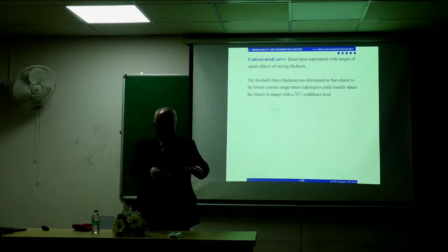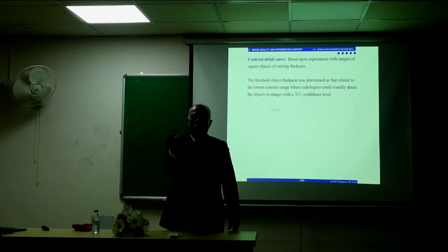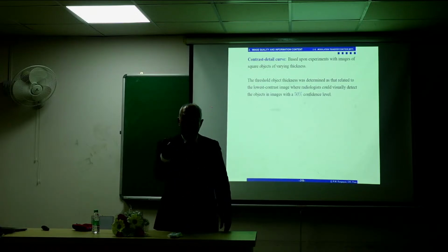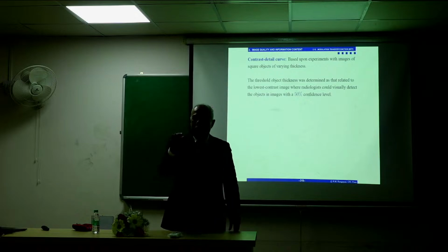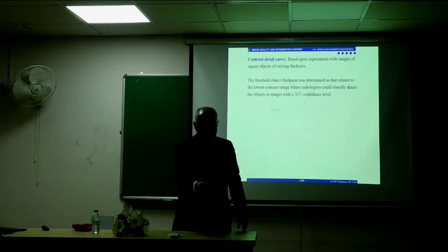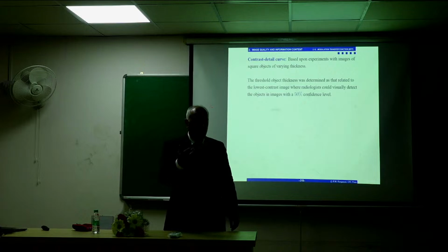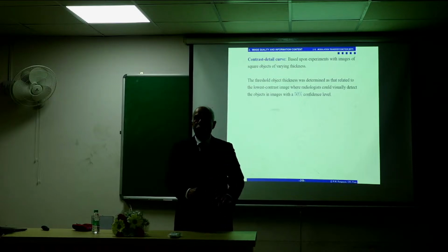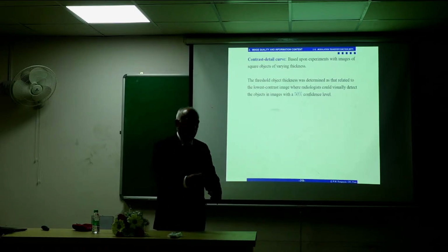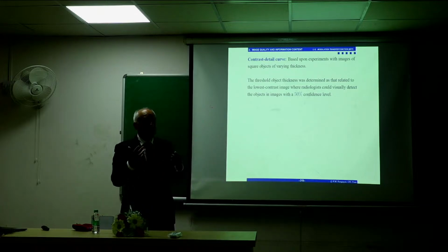So you make a phantom, a test image. Typically they use foils of gold, could be aluminum or some metal, different thickness and little pieces, squares or whatever you want, and different thickness and different size. If you just want contrast, just the thickness is varied. The thicker the material, the more the attenuation of the X-rays. And if it is very thick, there is more attenuation, so contrast is reduced. If it is very thin, X-rays pass through, you get higher contrast.